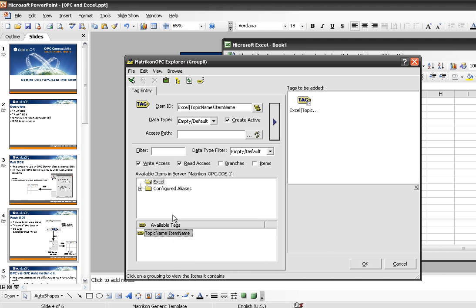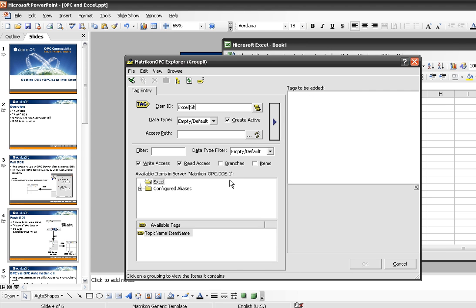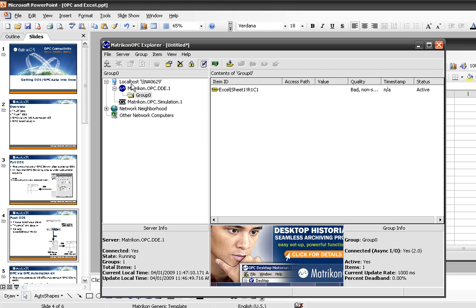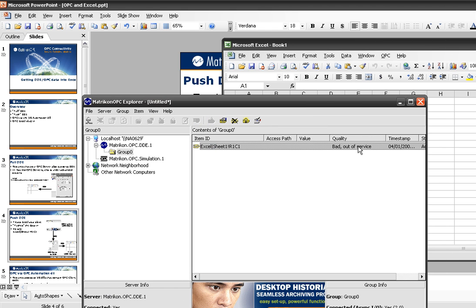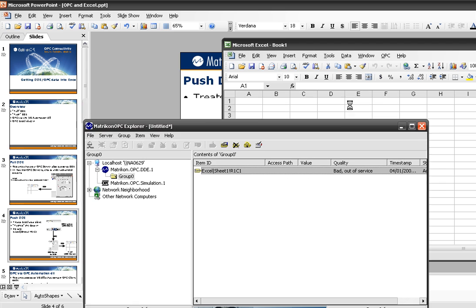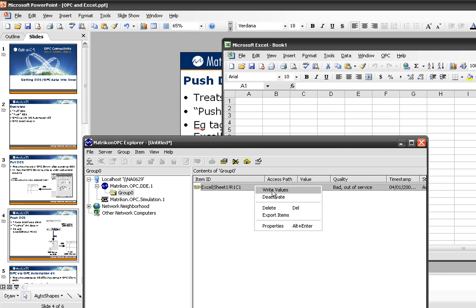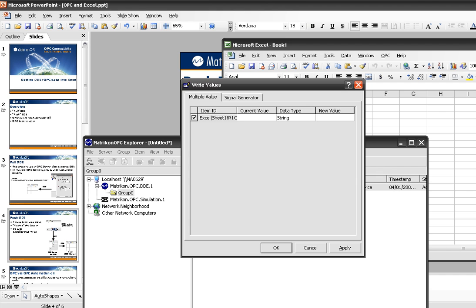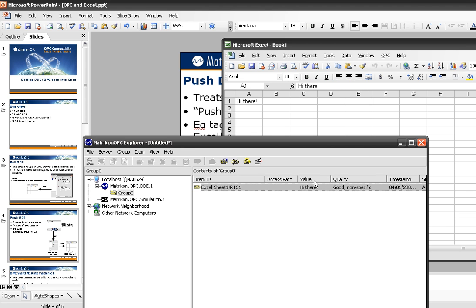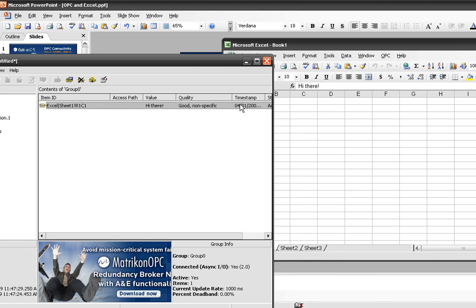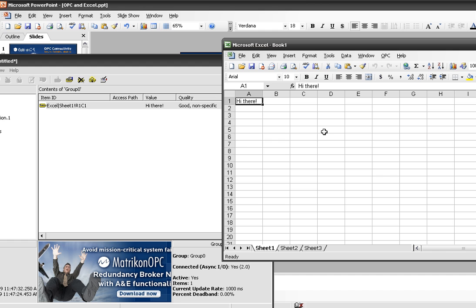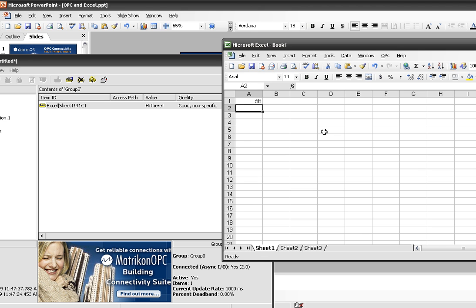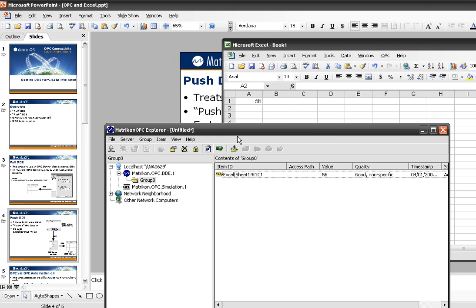There's no tag browsing with DDE — it just gives me a hint tag here. I know that I can go sheet1, row1, column1. It starts with bad quality because there's no data in that cell. I can either put data into that cell, or write data into it to give it a value and make it valid. You can see it popped over into Excel and it's also in my OPC Explorer. There's a one-second update rate. If I type 56 in here, it takes about a second to get over to my OPC client.